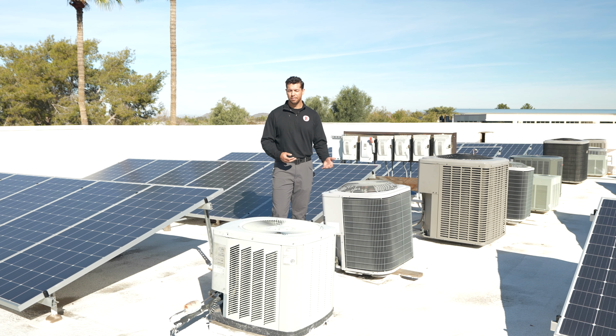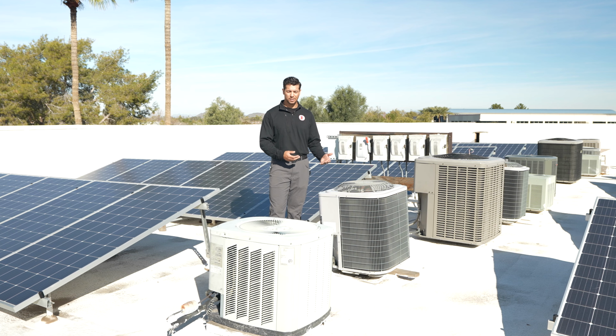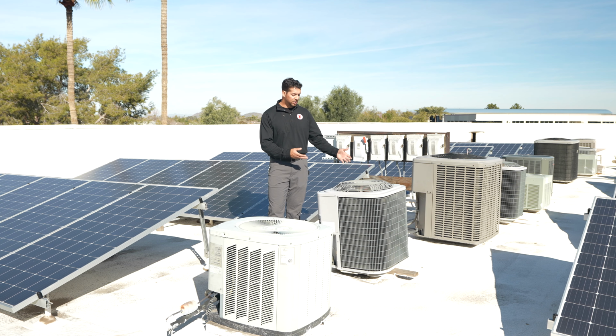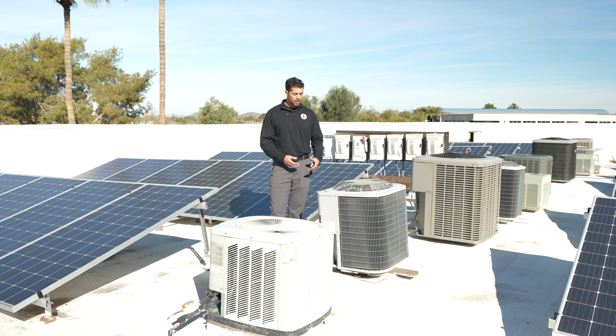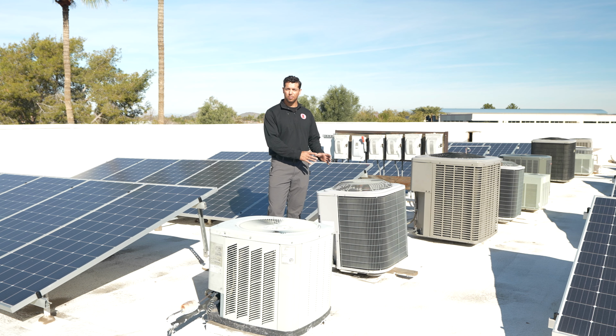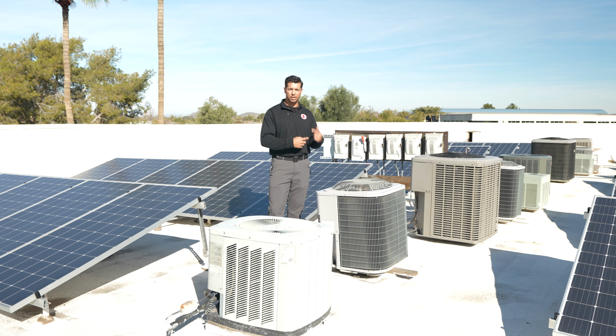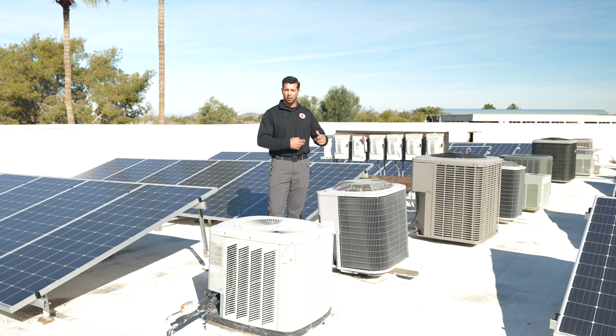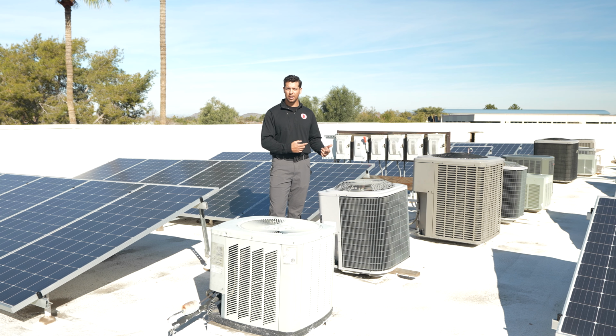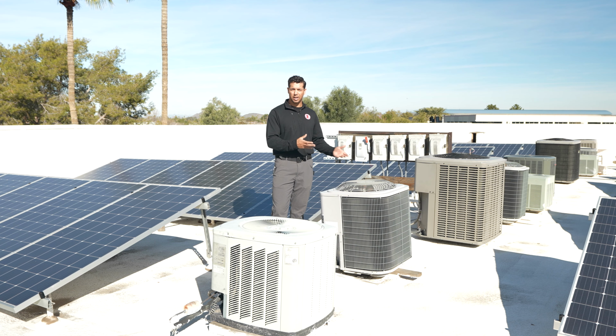I like to have one, and it might be a good idea for this purpose, and it makes for a good photo. But you can see this is significantly out of level. This unit has a compressor, a small motor with oil that circulates, and if it's out of level, components may not be oiled properly. So this is a defect we would like to include in our report.